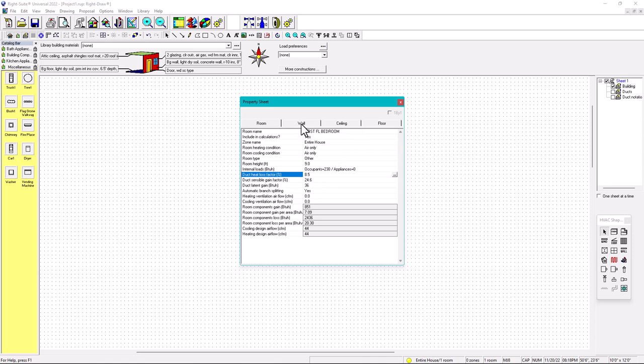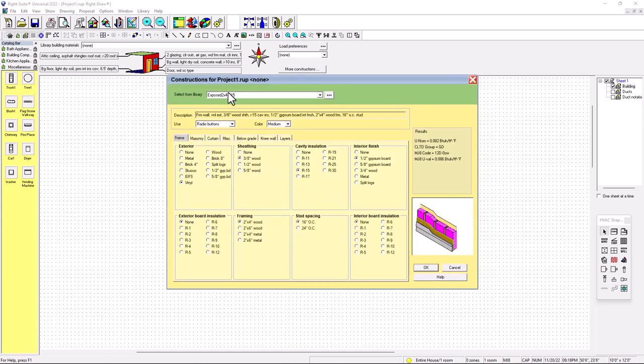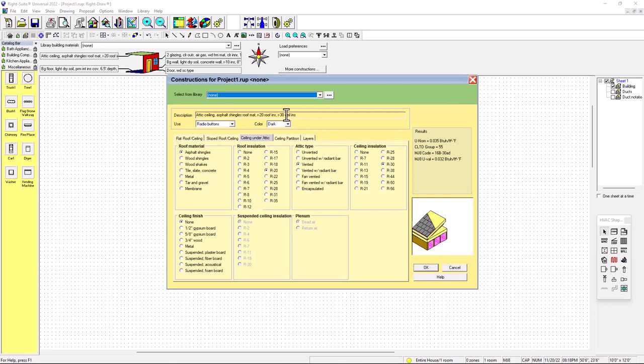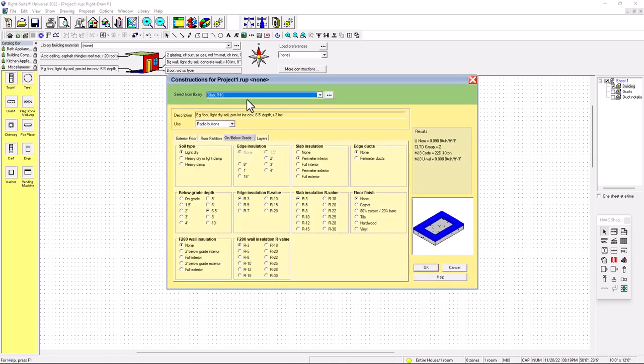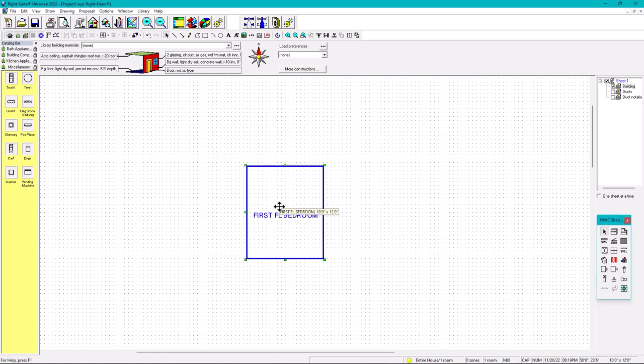Now we're going to go to the wall. For the exterior wall, we already have exterior wall R15 — you can always customize that depending on your library and create your own, as we showed in the other videos. Exposed 2x4 R15 is our exposed value for the walls. For the ceiling we're going to put R38 in the attic, and then for the floor we're going to put a slab — slab floor 10 with carpet. So this bedroom is already well defined.